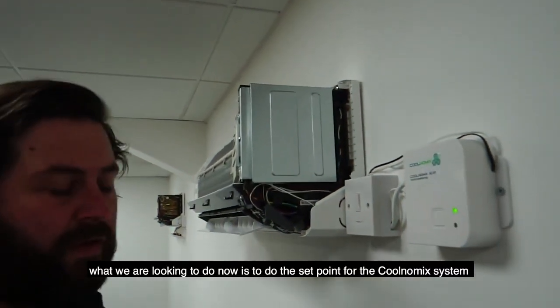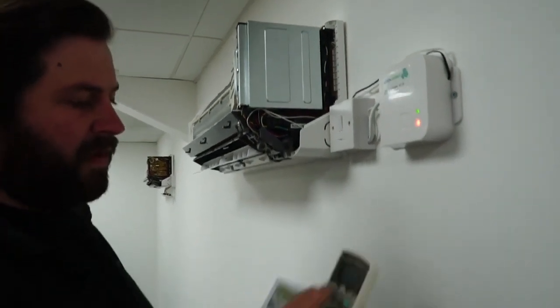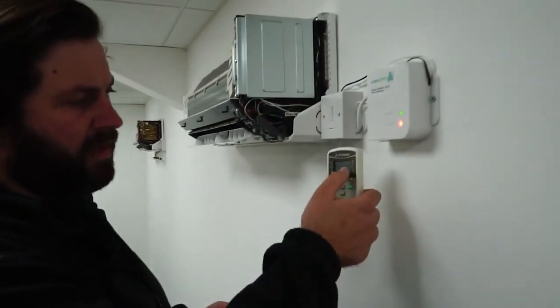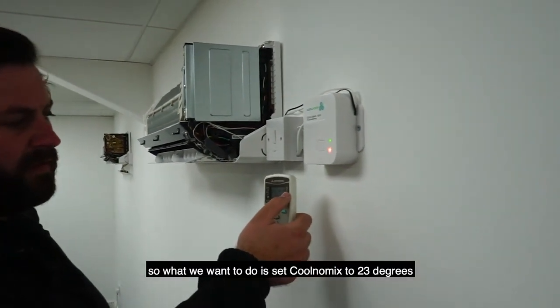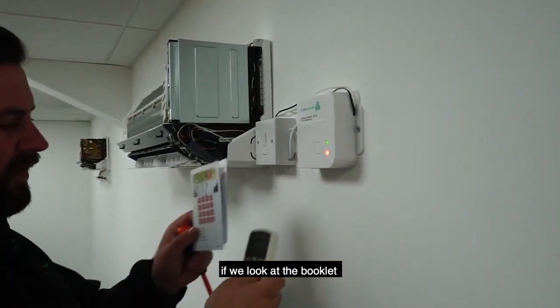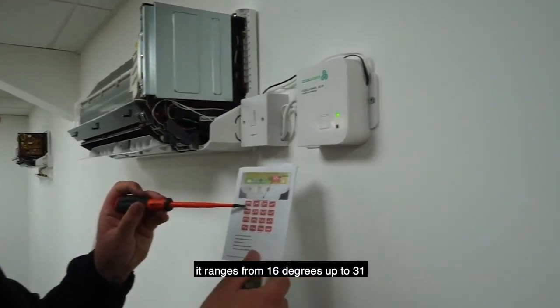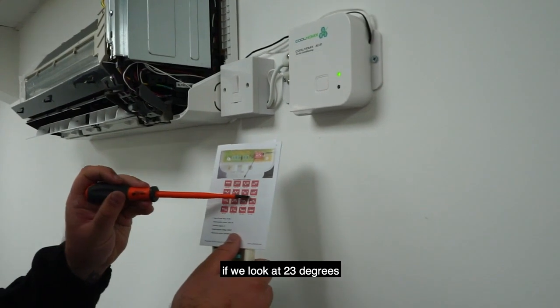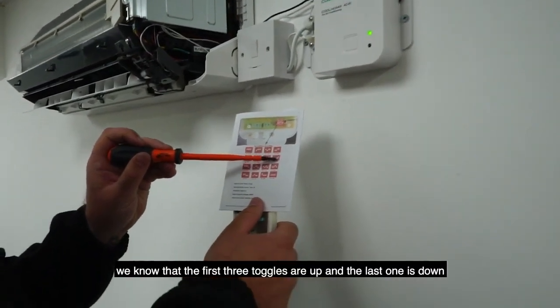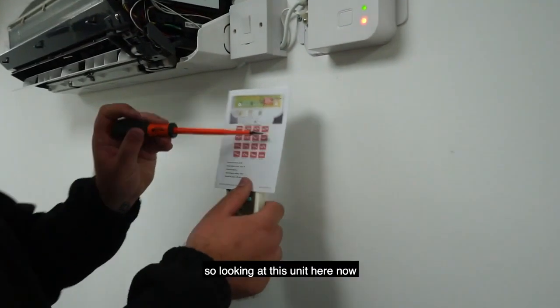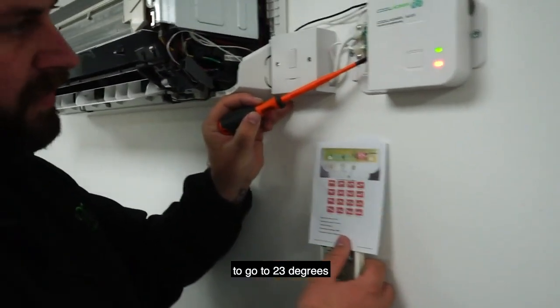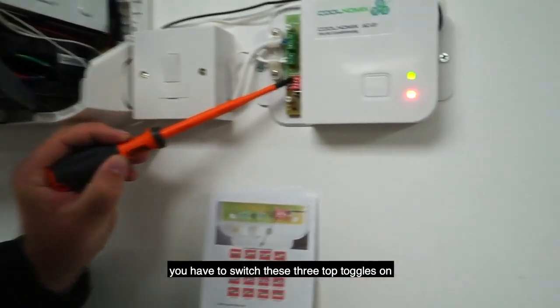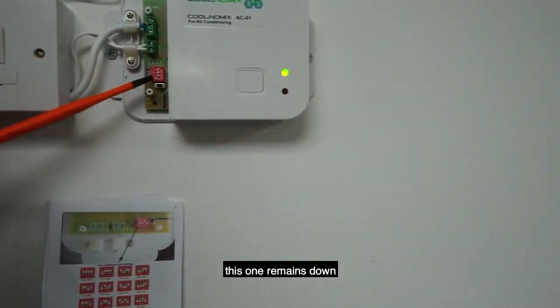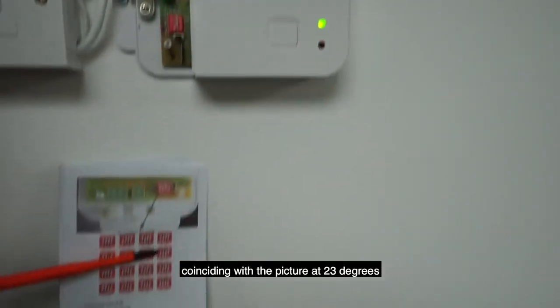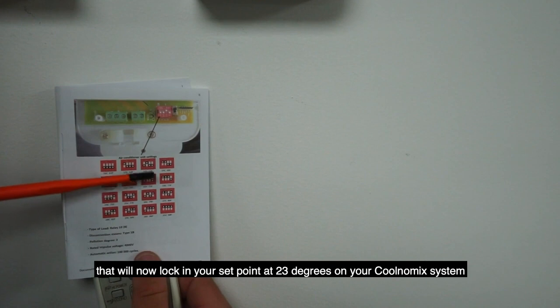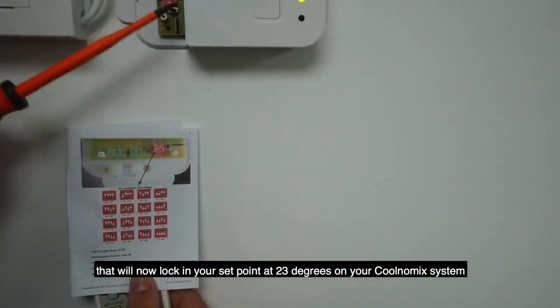Okay, what we're looking to do now is do the set point for the Coolnomix system. The remote control is set to 21 degrees and it's on cooling. So what we want to do is set Coolnomix to 23 degrees. If we look at the booklet, it ranges from 16 degrees up to 31. If we look at 23 degrees, we know that the first 3 toggles are up and the last one is down. So looking at this unit here now, to go to 23 degrees, you have to switch these 3 top toggles on. This one remains down, coinciding with the picture at 23 degrees. That will now lock in your set point at 23 degrees on your Coolnomix system.